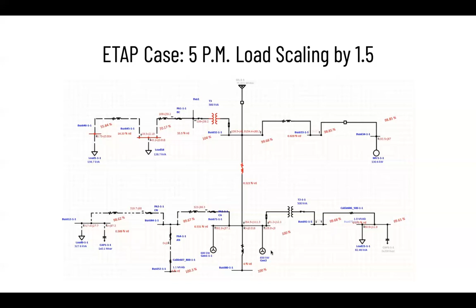system. As you can see for this case, our PV is generating 105 kilowatts, and our battery storage is delivering 562 kilowatts, which is a good sign. This lets us know that if our load gets multiplied by 1.5, our system will keep being able to sustain this, at least for this hour. And right here, we do have a few alerts, some violations. As you can see, we still have those under voltages from the residential area and those same current unbalances.